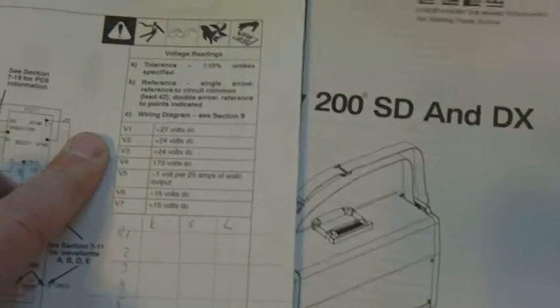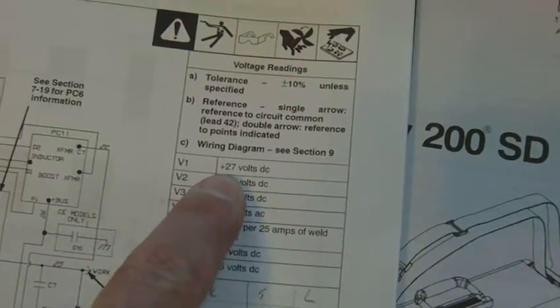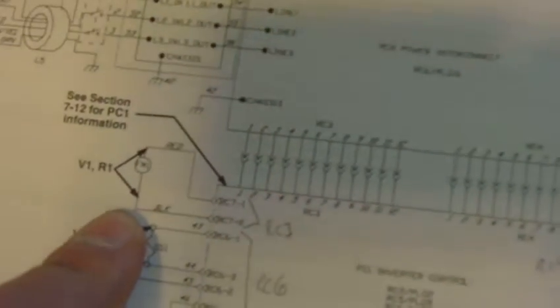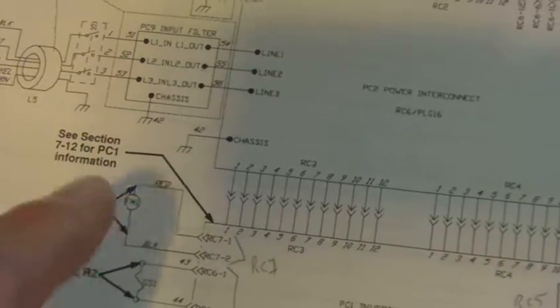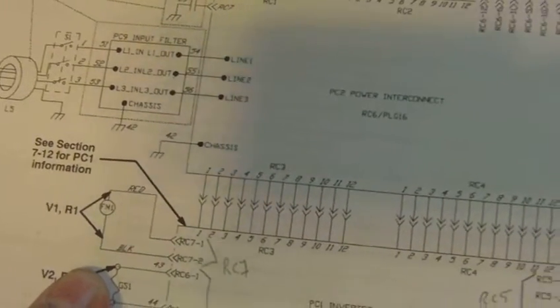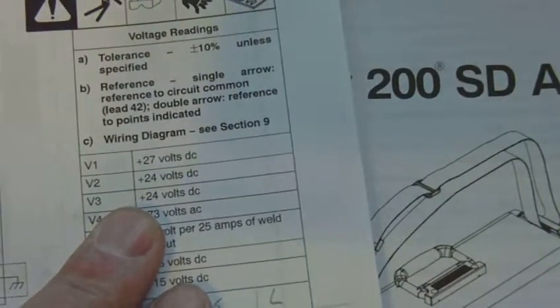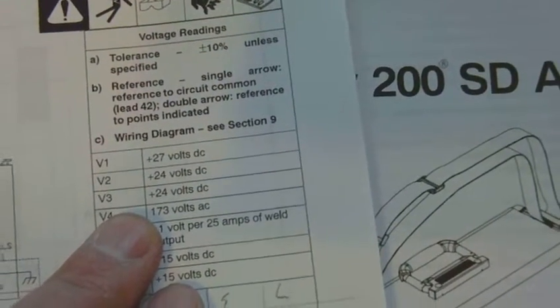But then that led me to doing the power on test. Hooked it up to the power, turned it on. V1 here, 27 volts. V1 is the power across the fan. I get nothing. It's 27 volt DC. There's 0. V2, 24 volt DC, same as V3.